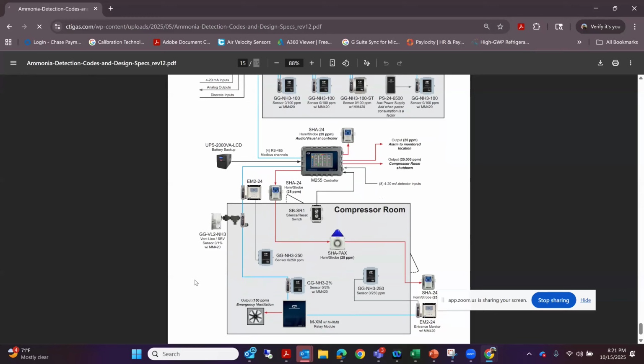And so if you have the daycare over there next to you, or if you have the school nearby, or your folks coming out and parking around the compressor room, and you've got some vent relief sensors out there that could drop a cloud like that down onto them, then a lot of times you might see that being used, and you could call that good engineering practice, just for the simple fact that you know when it happens. You're going to know when that release happens, and whether or not, if the weather's right, that cloud is dropping down on a parking lot. So I wanted to bring that up as well, because I know a lot of people go ahead and install these, and it's pretty common in our industry to put in a vent relief sensor.